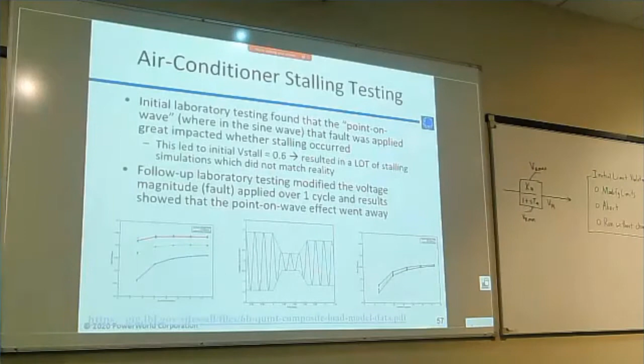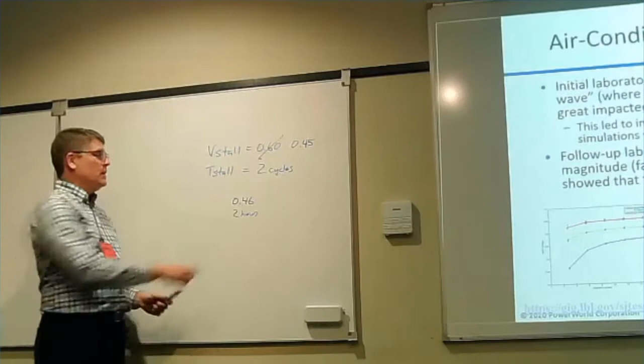And the problem with this is, what happens if the voltage drops to 0.46 per unit for 2 hours? If we're using this, it will not stall. If it drops to 0.45 for 0.0334 seconds, it will stall. So this is a little bit crude.